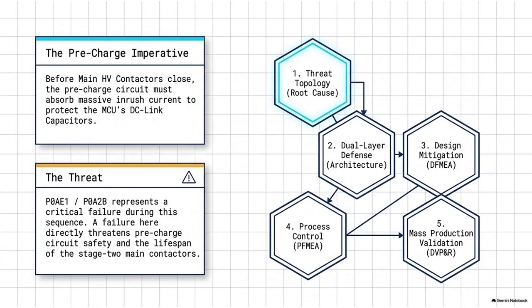Which means they weld themselves shut. Instantaneously. They micro-weld together, and suddenly you have a high-voltage system that physically cannot be turned off. Which fundamentally breaks the absolute primary safety requirement, the ASIL-D requirement of being able to isolate the high-voltage bus in an emergency. Exactly. You never ever want a contactor welded shut.